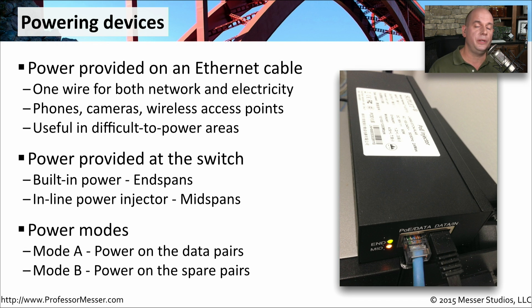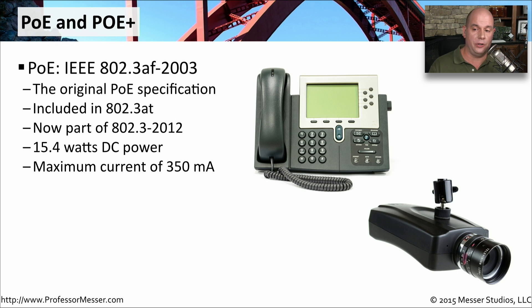You'll generally see two different kinds of modes for Power over Ethernet devices. One is Mode A, where the power is being placed on exactly the same wires that the data is traveling on. This uses a functionality called phantom power, and it means that you can run your data and your power over exactly the same copper. Mode B is one where data is on one set of pairs and the power is running on a completely different set of pairs, separating the power and the data inside the same cable.